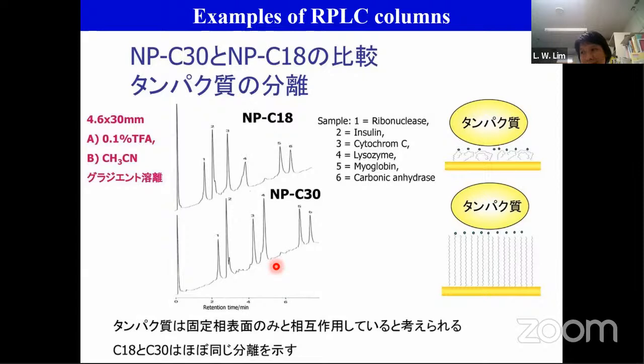Sometimes it also depends on your sample. Sometimes it's also because of your detector. If the detector has a weak lamp, because the company that sells you the detector will say you can use the lamp for 2000 hours.